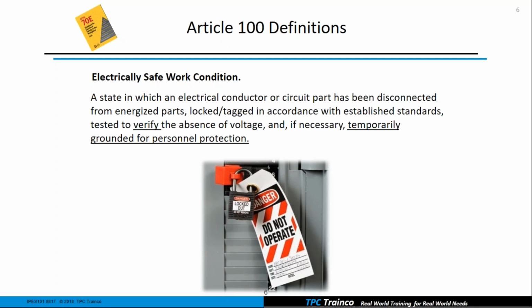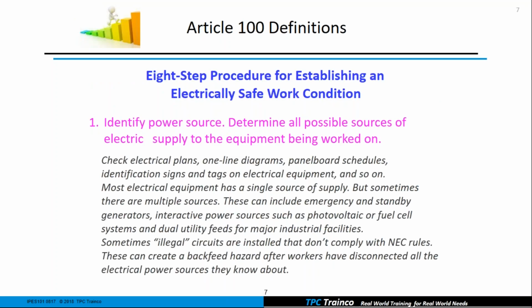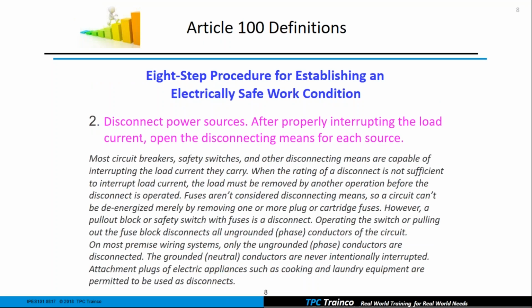But in this definition now, you can see that they have put in the words verify the absence of voltage, and if necessary, temporarily grounded for personnel protection. Of course, that happens a lot of times with higher voltages, where we have to put those ground straps on, but they wanted to get that in the definition. So I did mention that there are now 8 steps to establish an electrically safe work condition. This is one of the steps that we always had. We had to identify all possible sources of power coming to the equipment. And this step also was one that we had, to properly interrupt the load current and then open up the disconnecting means.